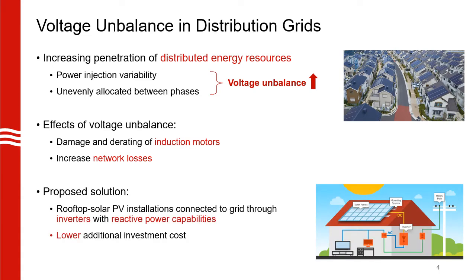In our work, we mitigate voltage unbalance by utilizing the reactive power capabilities of power electronic inverters. Most solar PV systems are typically connected to the grid via these inverters which can offer reactive power support. Since we are using existing equipment, this could be a very cost effective solution.